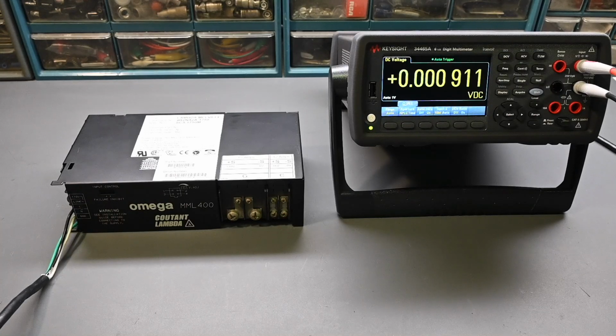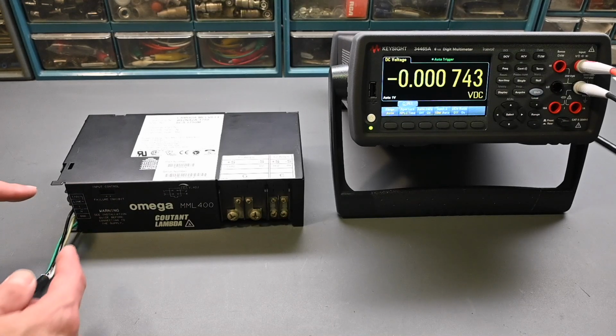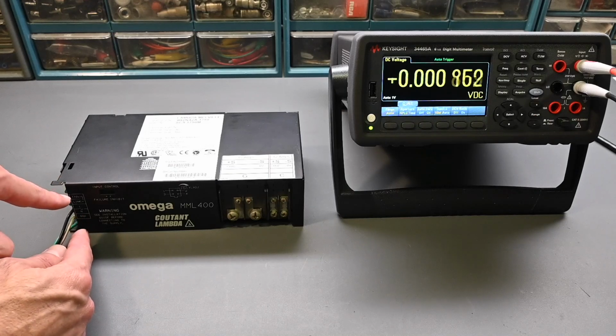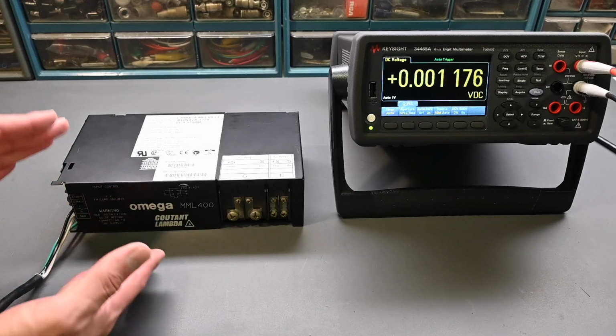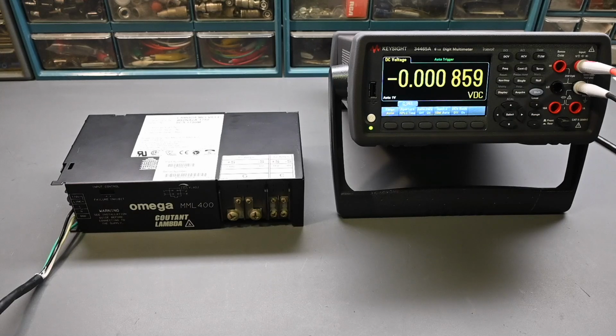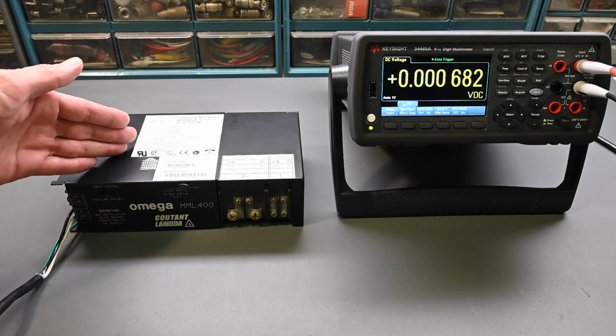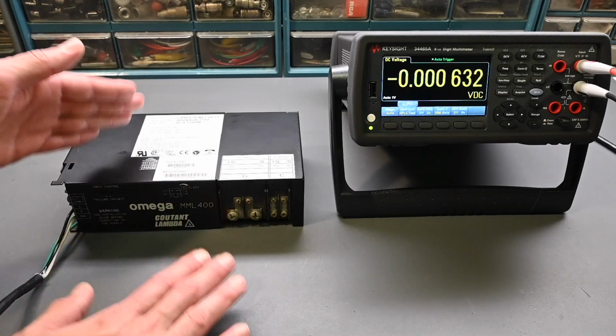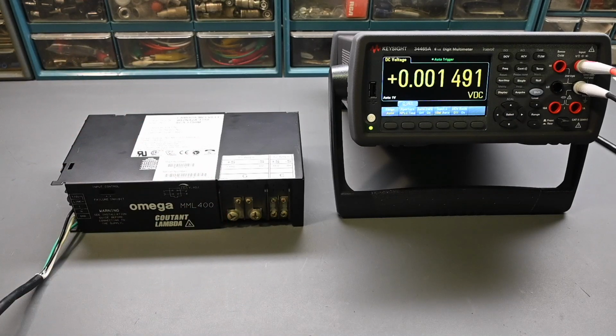And remember, an isolation transformer doesn't protect you from being shocked across that AC line. There's still a voltage potential that will be a very nasty, if not lethal, shock. What the isolation transformer protects against is contact from the AC line to ground. So that's where it's adding that protection. Now that gets into a whole other topic with isolation transformers and so forth, but just know that you do need to be using that.